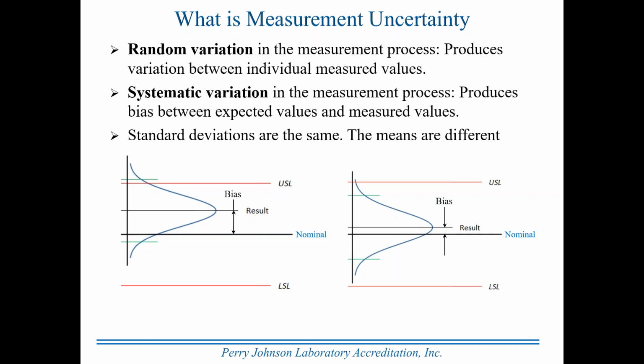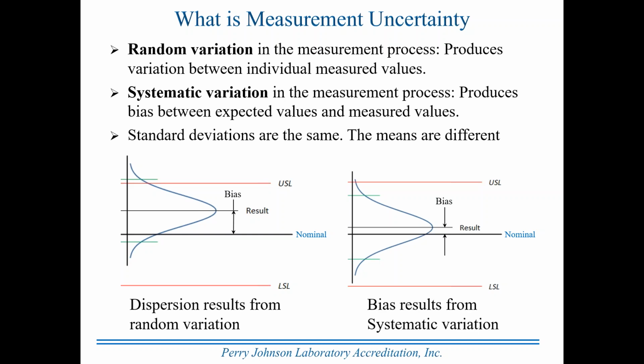So systematic variation in the measurement process produces the bias. Systematic variation, oftentimes on adjustable equipment, can be eliminated or minimized, reduced, bringing a piece of equipment that was outside of specification back into specification. Dispersion results from random variation. Now, random variation is random because we don't know what it is or where it comes from. There isn't anything we can specifically identify and fix or eliminate to remove random variation. You can think of it as the variation that is remaining after all identifiable sources of variation have been addressed. On the other hand, the bias results from systematic variation.